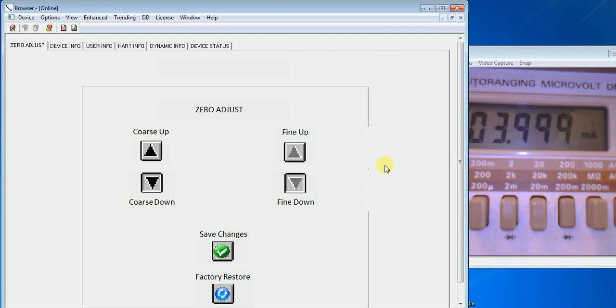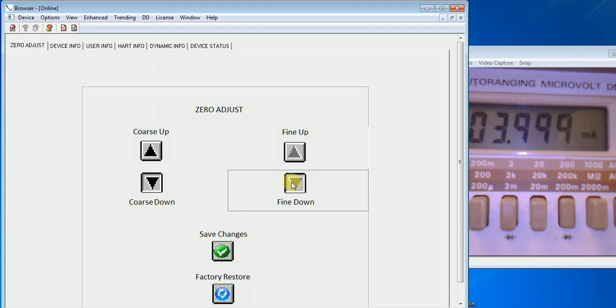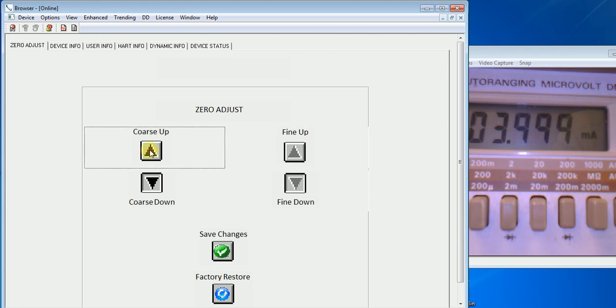The unit may not be at exactly 4 milliamps. There is a tolerance on this and we could be at 4.003 or 4.005. These adjust in steps. You may not get exactly 4 milliamps, but you will be able to get it within the specification of the unit.